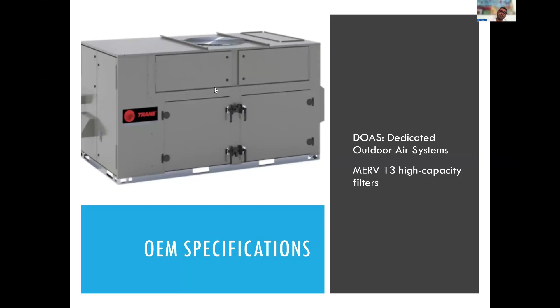Filtration requirements. As I said, pre-filters, MERV 8 pleated filters; final filters, MERV 13 rigid. Molecular carbon filtration, we're looking for activated carbon here. And for HEPA, in those very rare cases, 99.97% efficiency, tested on site.